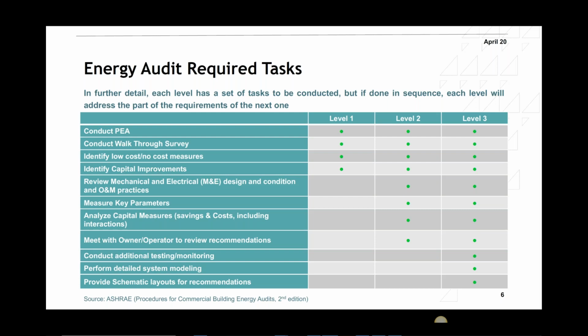Now with level 2, you do exactly what you've done for level 1, plus you need to review the mechanical and electrical design, condition, and O&M practice, so you do more detailed analysis. You would need to do measurements. So you need to do measurements on, let's say, electrical power consumption for the chiller, what is the kilowatt per ton for the chiller. You look at the fans, what is the watt per liter per second, what is the amount of fresh air or outside air flow going into the building, what is the amount of exhaust flow. The more measurements you make, the more accurate your assumptions would be. And the longer the period you have it, especially for variable loads, the better the quality of the energy audit. You need to do analysis for the capital measures.